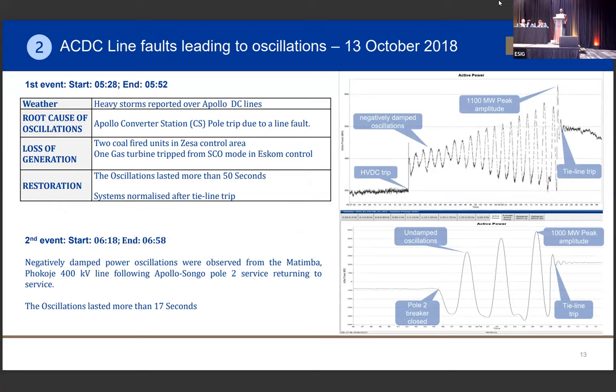It was, I think, pole one. Pole one is the pole that we use as a carrier for communication between one of the power substations in the north of South Africa and Songo in the north, to give it a reference angle. Because of that pole one, they didn't have that carrier, and the power system stabilizer didn't operate or malfunctioned. So we started having oscillations, and the oscillations were negatively damped. Then at around peak mode, the tie line, the line that connects the two control areas, tripped, or the power swing relay operated. The oscillations lasted about 50 seconds.